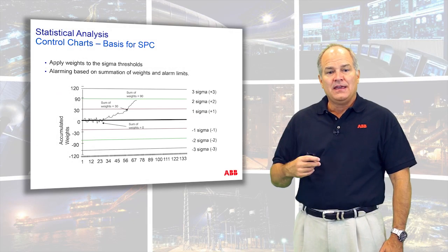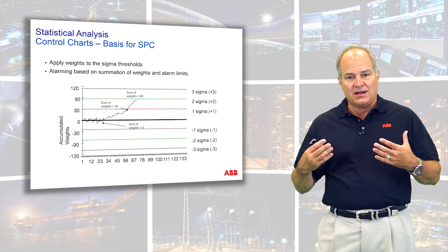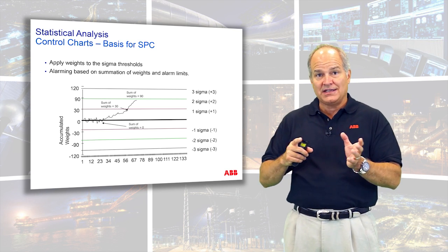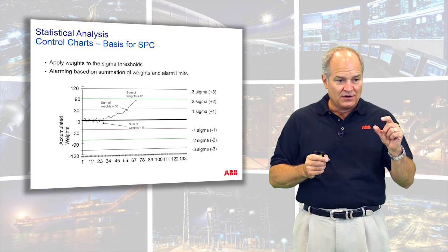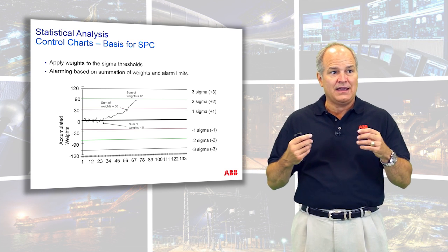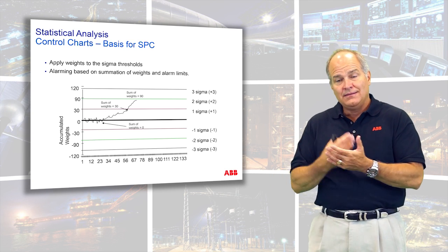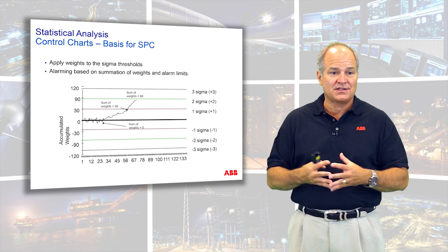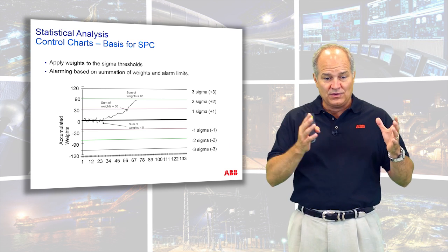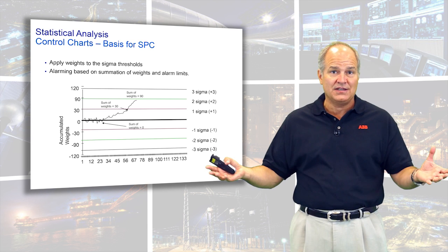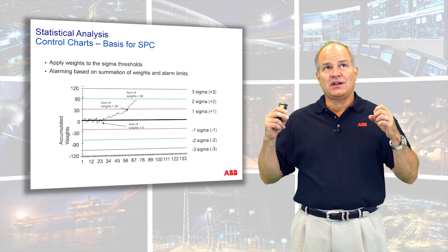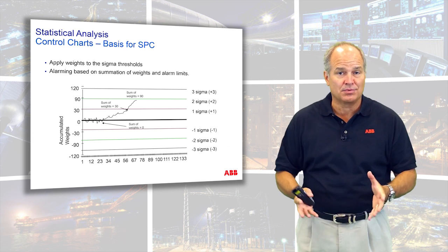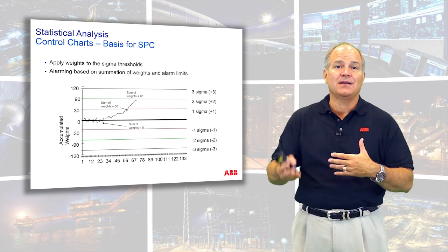Now, a control chart looks like, and this is now, we use the raw data to calibrate our control chart, and then what we're trying to do is alert the operator that something's broken. So in the world of statistical process control, it's called SPC, are these control charts. And they're looking at the normalcy of the data, and if the data becomes abnormal, something's broke. This is Deming's theories on statistical process control, and it works really good when you're measuring widgets or even continuous process control. Is you kind of benchmark the normalcy, and when the normalcy changes, something's broke. You need to stop and fix it. That's the concept of SPC.